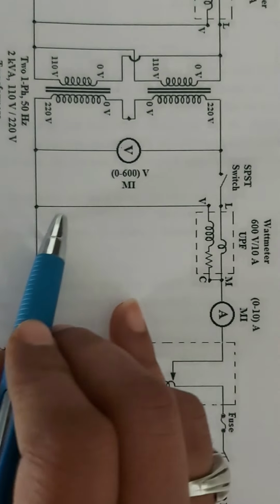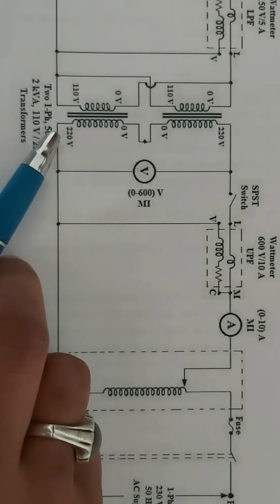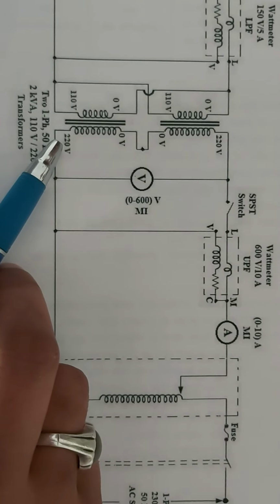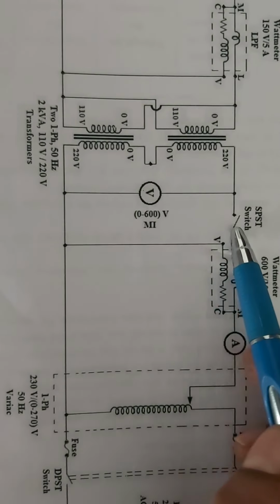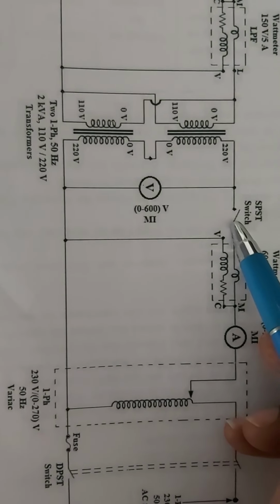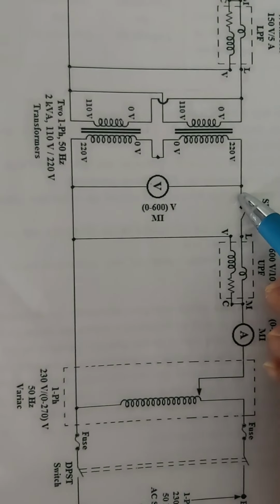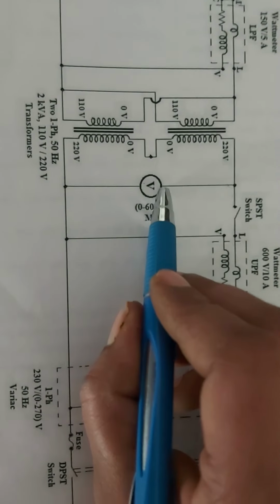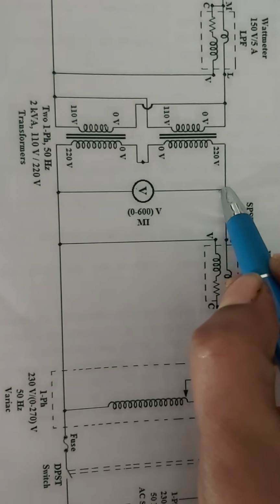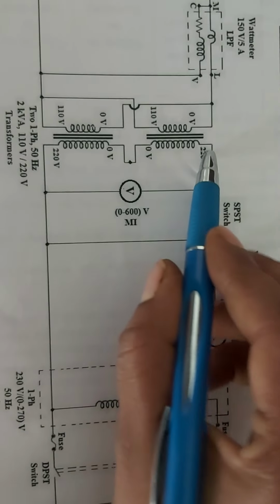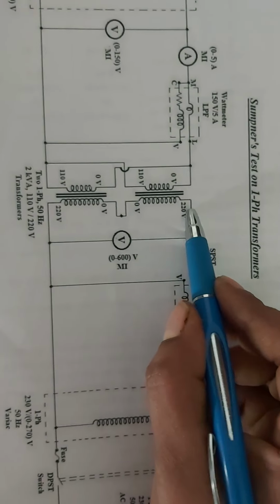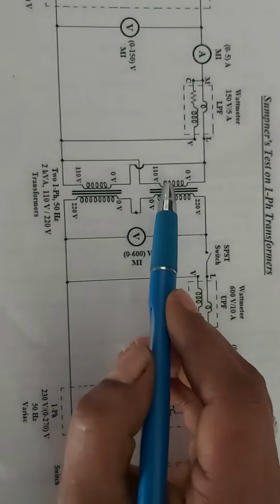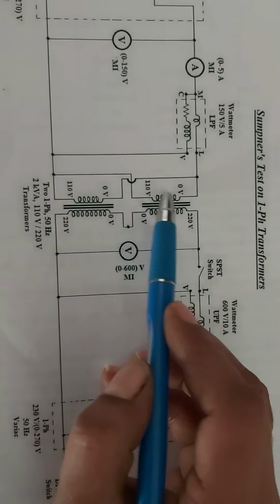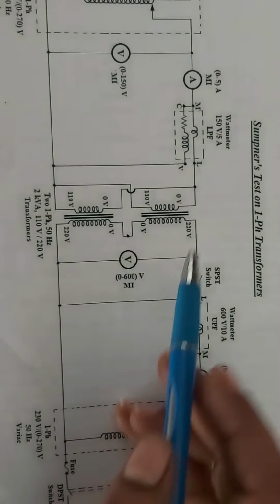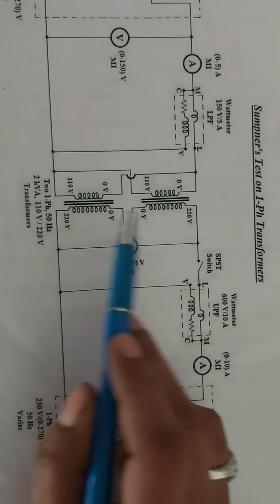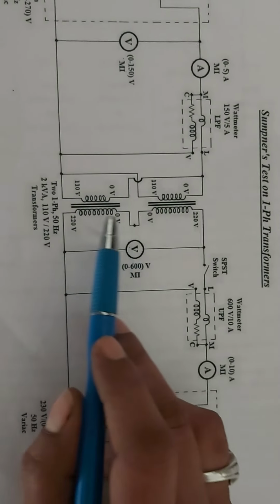From the V we take one wire that is connected to the 220 volts of the second transformer secondary winding, and L is connected to the SPST switch. Here the SPST switch phase terminal and neutral terminal are connected to the voltmeter positive, that is the common point, and one wire is connected to the 220 volts of the first transformer secondary winding. Here in this figure, the two transformer primary windings are connected in parallel, and the two transformer secondaries are connected in series.